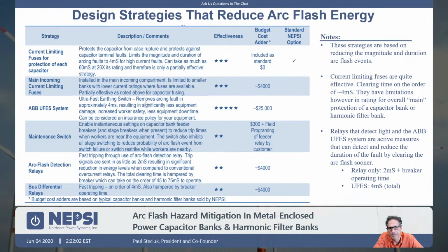So we're into strategies here that reduce the energy, and these are things that reduce the magnitude of the fault current. Current limiting fuses would be an example, and things that reduce the time. In particular, we have bus differential relays and arc flash detection relays. Both of these relays can interrupt faults very quickly. The arc flash detection relay that's offered by Schweitzer, for instance, the 751A, will detect an arc flash event within 2 milliseconds and send that trip signal. But that trip signal is going to a breaker, and that breaker is going to take another 3 to 5 cycles to operate.